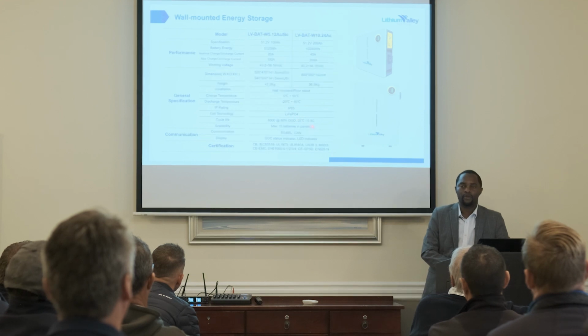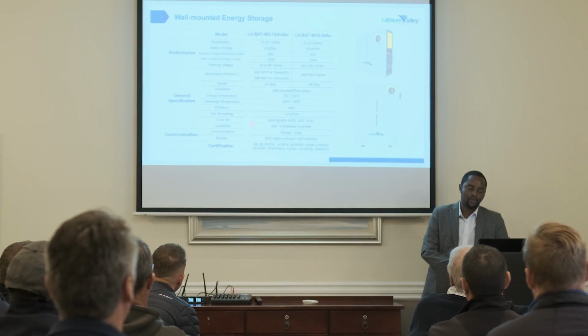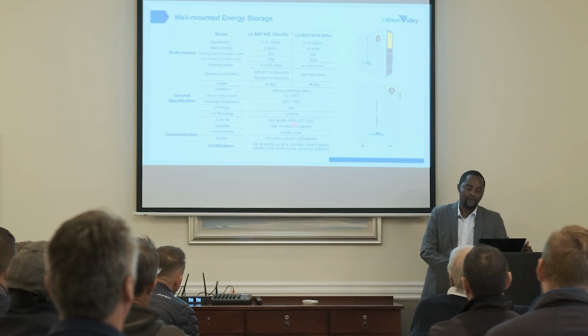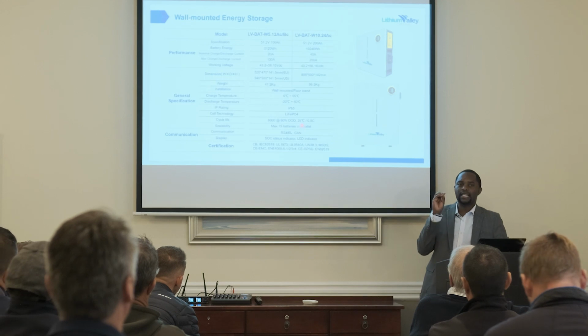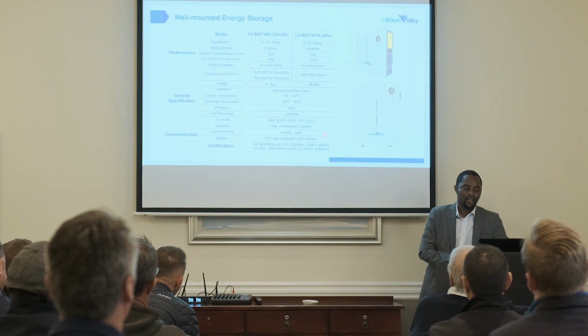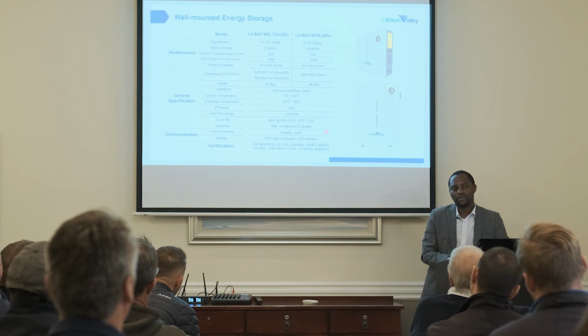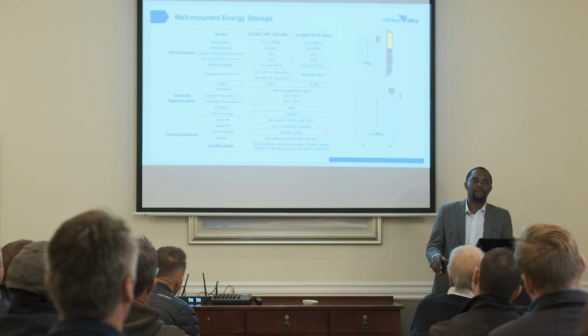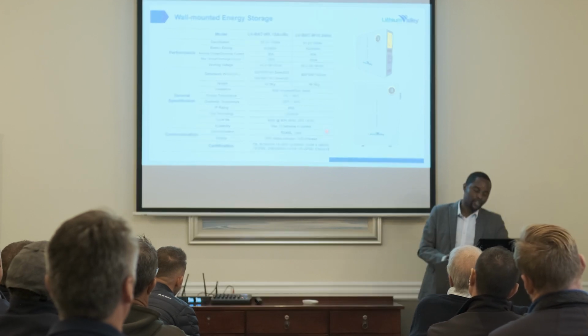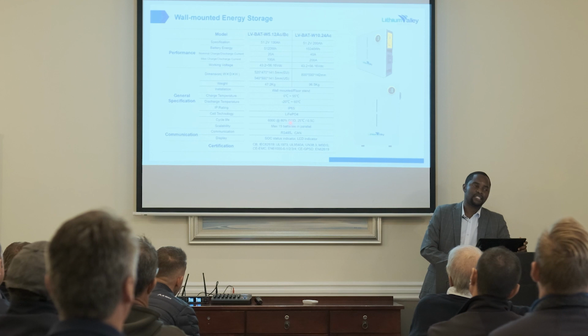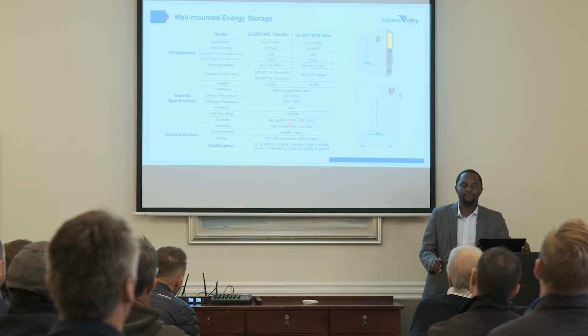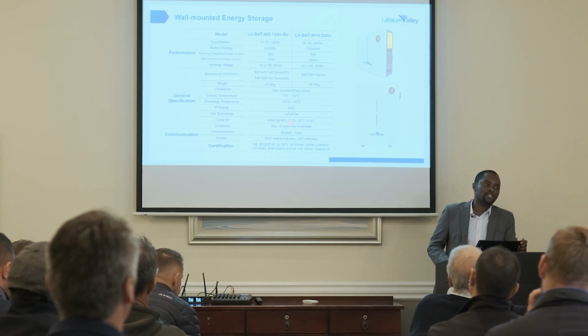Then this line where it says 0.5, this is the testing. So when they tested the number of cycles, they get to 6,000, and they were testing using 0.5, continuously discharging 0.5 from the batteries. So this is what they are just telling us here. There's also a misconception of thinking that when you get to 6,000 cycles, your battery is dead. No. When you get to 6,000 cycles, your battery has reached end of life. End of life means you have lost at least 20% of your capacity. So if it was a 5 kilowatt, after 6,000 cycles, it's now a 4 kilowatt.